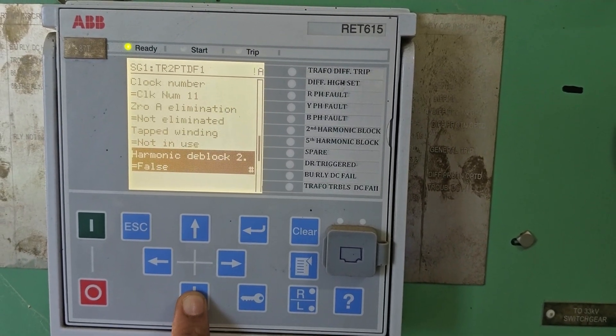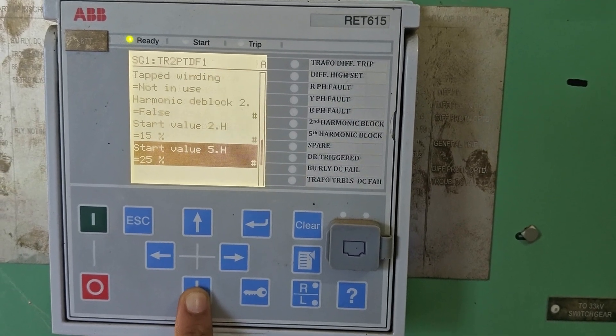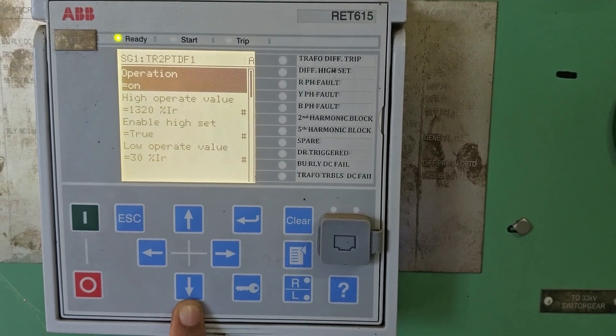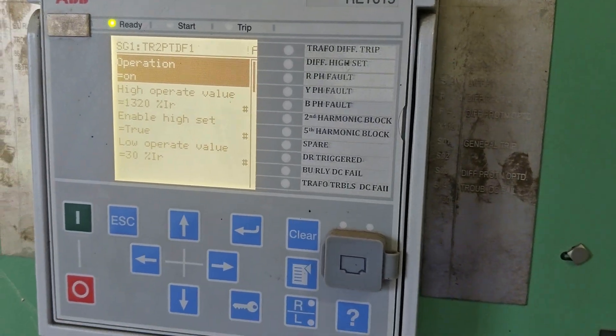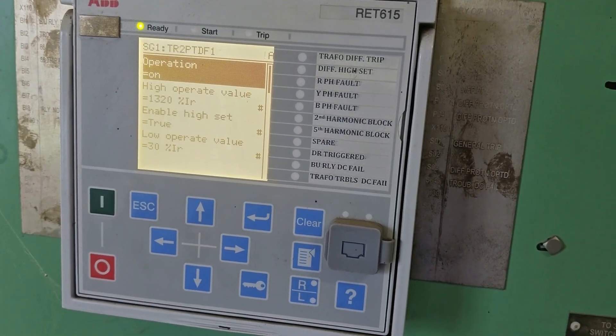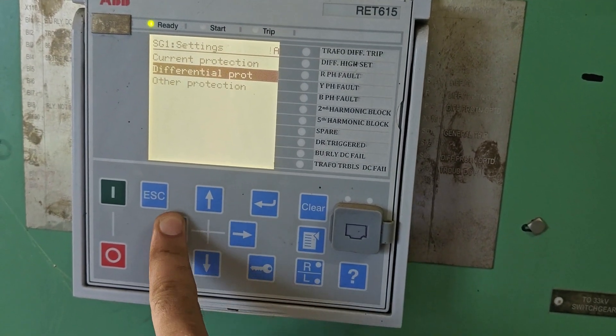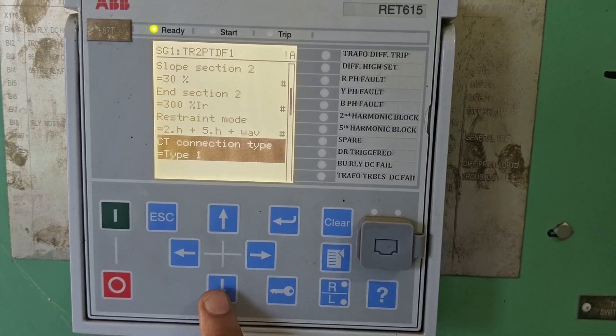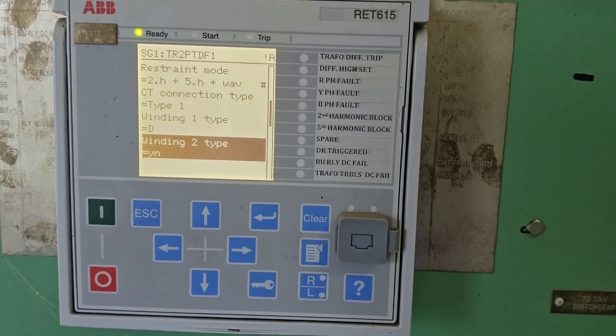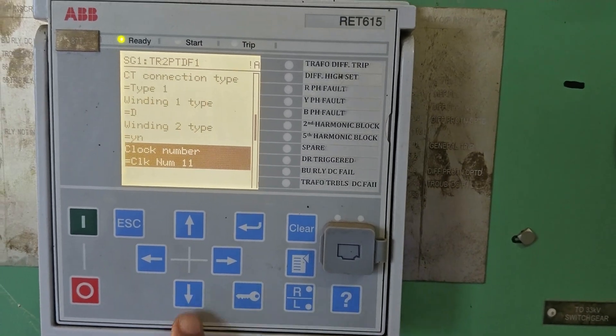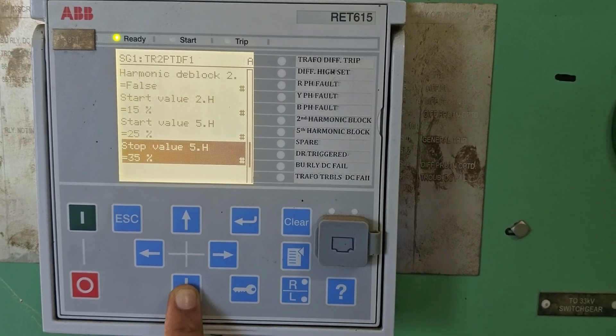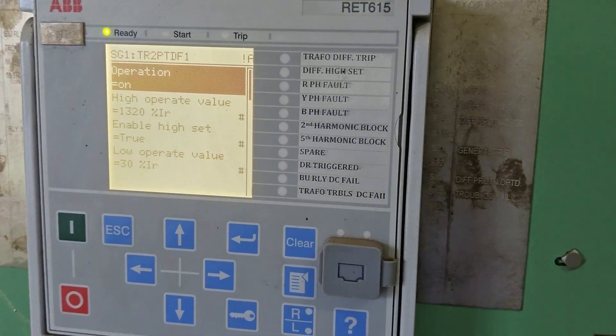The zero sequence is not eliminated. This signifies that the zero sequence current is not omitted by the transformer's configuration or by the relay setting. This means the relay must consider zero sequence current when making tripping decisions — the relay includes zero sequence current in its differential current calculation, which affects the relay's sensitivity to ground faults or unbalanced conditions.